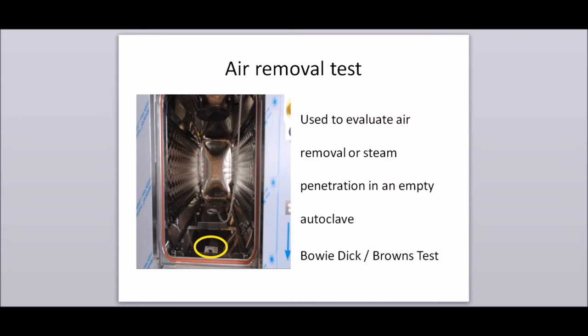Air removal test: a diagnostic test used to evaluate air removal and steam penetration in an empty autoclave. Examples include the Bowie-Dick test or Brown's test.